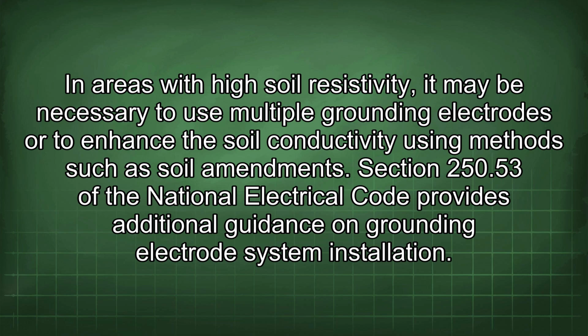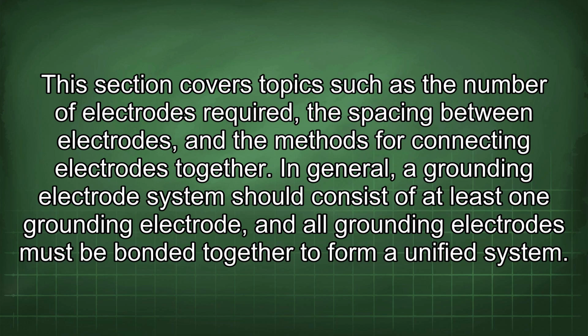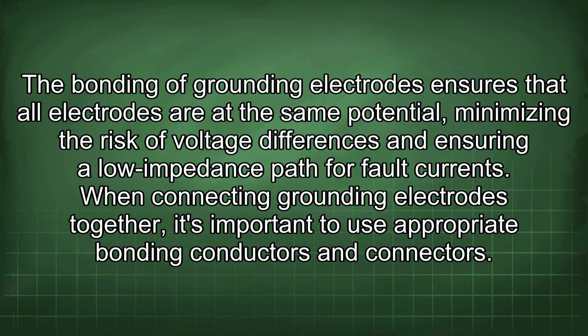Section 250.53 of the National Electrical Code provides additional guidance on grounding electrode system installation. This section covers topics such as the number of electrodes required, the spacing between electrodes, and the methods for connecting electrodes together. In general, a grounding electrode system should consist of at least one grounding electrode, and all grounding electrodes must be bonded together to form a unified system. The bonding of grounding electrodes ensures that all electrodes are at the same potential, minimizing the risk of voltage differences and ensuring a low impedance path for fault currents.